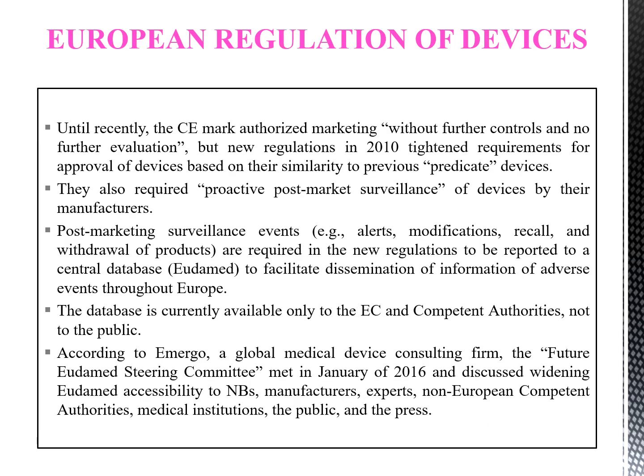Until recently, CE mark authorization was without further controls and no further evaluation. But new regulations in 2010 tightened requirements for approval of devices based on their similarity to previous predicate devices. They also require proactive post-marketing surveillance of devices by their manufacturers. Post-marketing surveillance events, for example alerts, modifications, recalls, and withdrawals of the products, must be reported to the central database, which is EUDAMED. This is a central database to facilitate dissemination of information on adverse events throughout Europe. The database is currently available only to the EC and competent authorities, not to the public.